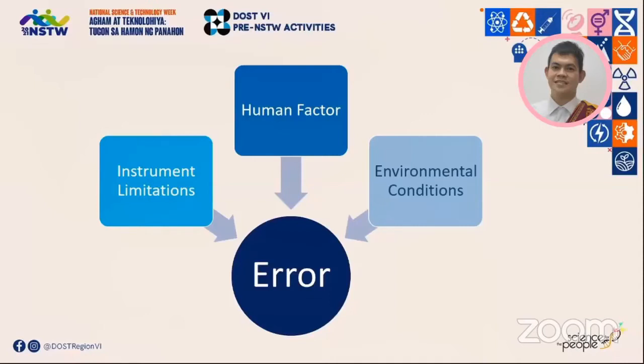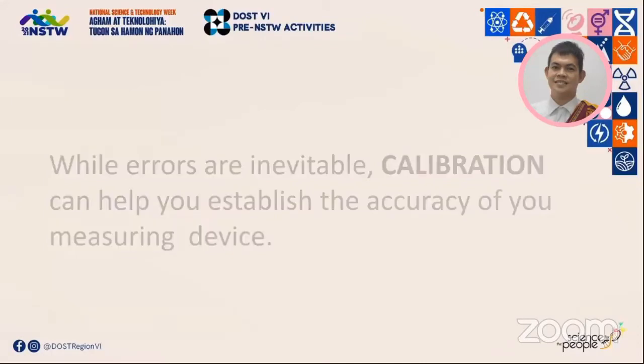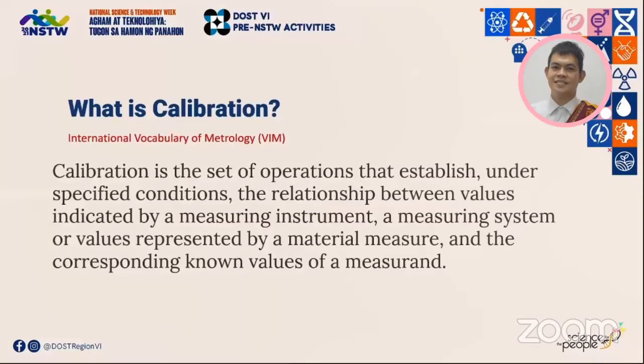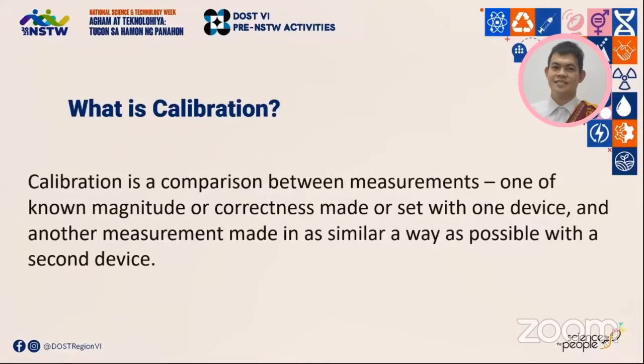Although there is no such thing as a perfectly accurate measurement due to some errors here and there, our pursuit for better measurement should not be hindered. There are in fact ways for us to circumvent these errors, one of which would be calibration — a process that can help us establish the accuracy of our measuring device. According to the International Vocabulary of Metrology or VIM, calibration is a set of operations that establish under specified conditions the relationship between values indicated by a measuring instrument or measuring system and the corresponding measurement.